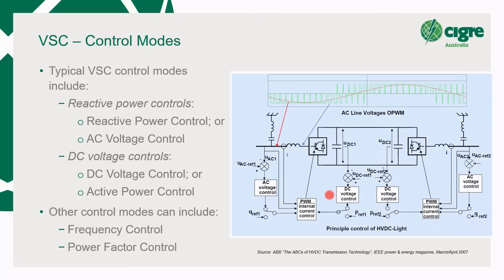hang on, I'm trying to think this one through. I haven't been in a position where I've had to define that, but typically your rectifier would be your active power controller if you look at the traditional HVDC, and your inverter would be your DC voltage control source. But with VSC, I've seen them operated in both, so I can't think of a smart answer to that off the top of my head. Sorry.